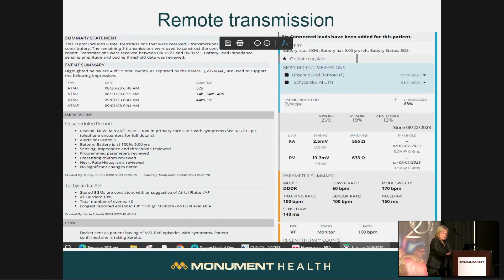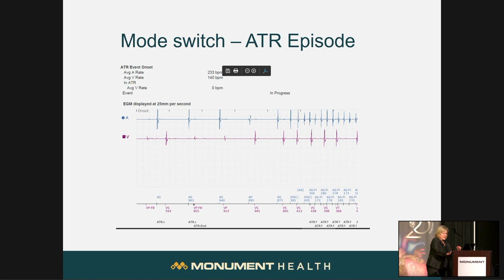So this is what a mode switch looks like when the patient goes into atrial fibrillation. You can see on the upper line is the atrial beat, and then the ventricle follows. The first few beats are normal pacing. Then it goes into atrial fibrillation and rapid ventricular response. And so the device will switch modes so that it won't try to pace through the atrial fibrillation. It'll only pace in the bottom chamber if it needs to. And then when the ATR episode ends, hopefully it ends, then it goes back to pacing dual chamber again.